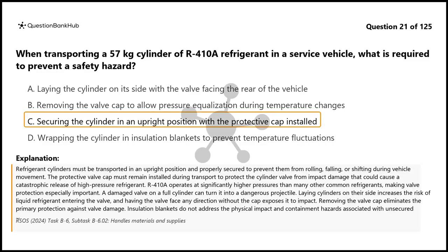Refrigerant cylinders must be transported in an upright position and properly secured to prevent them from rolling, falling, or shifting during vehicle movement. The protective valve cap must remain installed during transport to protect the cylinder valve from impact damage that could cause a catastrophic release of high-pressure refrigerant. R410A operates at significantly higher pressures than many other common refrigerants, making valve protection especially important. A damaged valve on a full cylinder can turn it into a dangerous projectile.